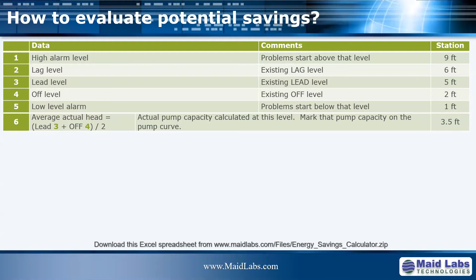Probably right below that high alarm level. What is the actual lag level, the actual lead level, the off level, and if you want to add a reference, an alarm low level, you can also enter that. Next step is to calculate the actual average level for which a pump capacity is calculated during a drawdown. In this case here, we just do the average between the lead level and the off level, and that gave us 3.5 feet. Then we do a drawdown, okay, and we arrive at 500 GPM.